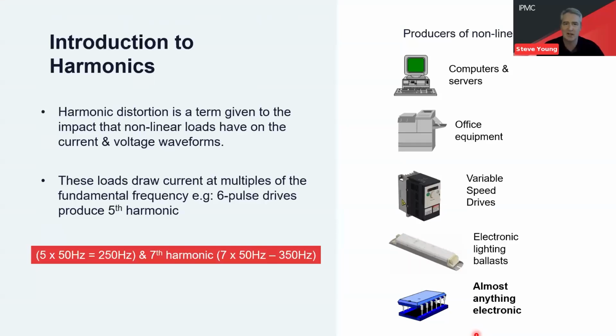So on to harmonics. Harmonics is a term that we give to the impact that these modern electronic loads have, firstly on the current waveform, and then, in an Ohm's law relationship, ultimately on the voltage waveform. If we look at some of the producers of nonlinear current, typical things that we see in everyday applications now, we really can't get away from them. Most applications are predominantly harmonic nonlinear loads now. Computers and servers, office equipment, electronic lighting ballasts, and probably most importantly, variable speed drives. In fact, almost anything electronic has its own harmonic signature. The way to think about harmonics as we work through these slides is that they ultimately manifest as heat and vibration and have a significant impact on the application.